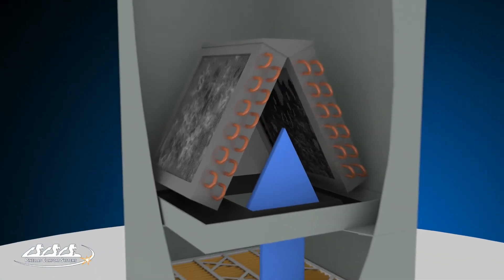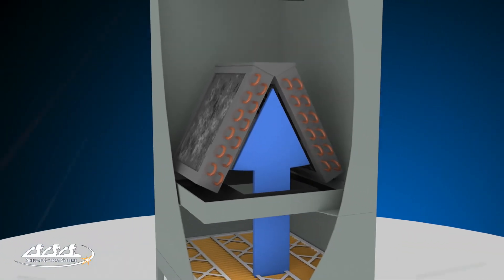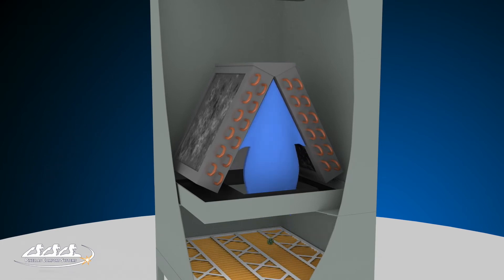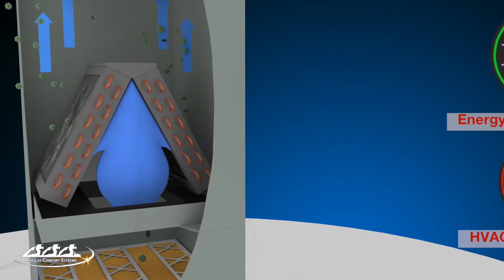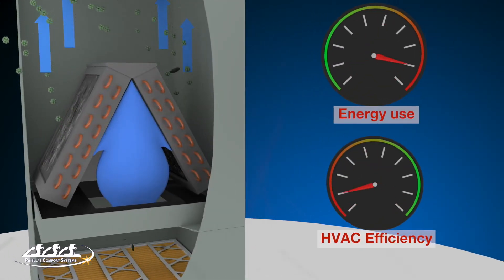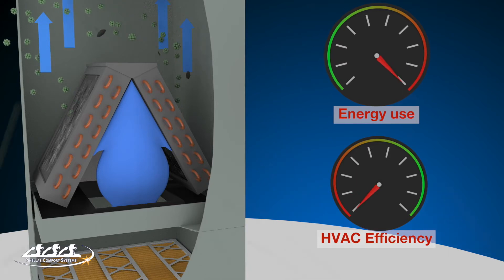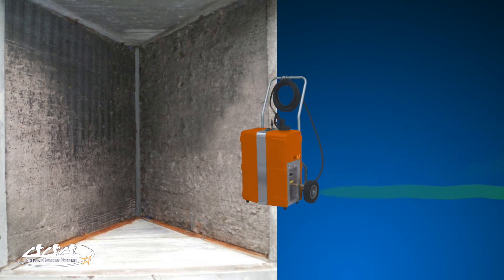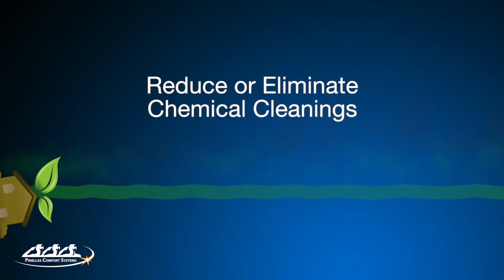A severely bio-clogged coil can cause excessive air resistance, and the insulating characteristics of the bio-growth reduces the thermal efficiency of the system. The result is the air conditioner works harder, increasing energy use and accelerating wear and tear. Clogged coils and drain pans periodically require expensive chemical cleanings, which are not good for the environment.